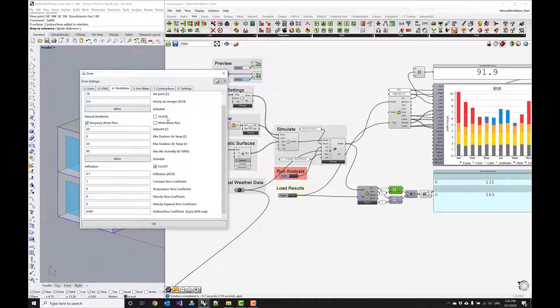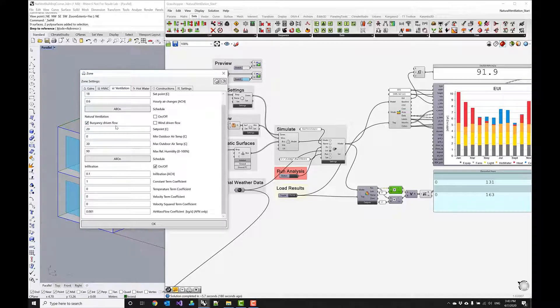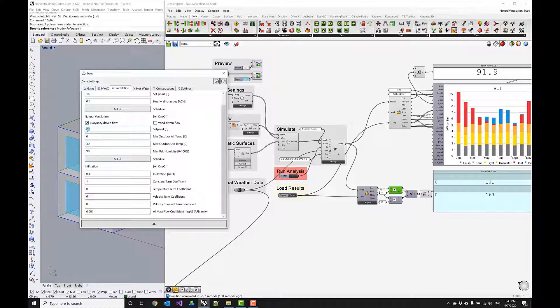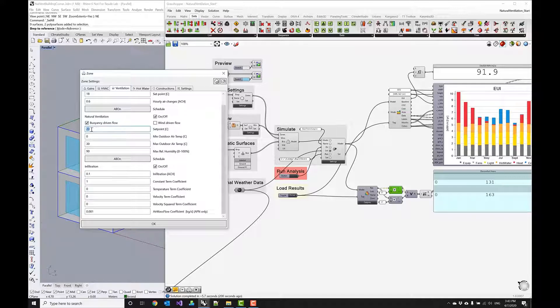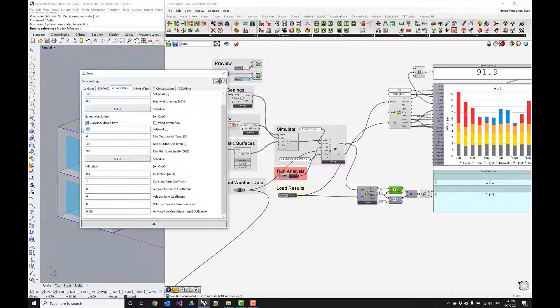So in this tutorial we want to use buoyancy driven flow only and we can think of this as a worst case scenario if there's no wind at all we can certainly count on the buoyancy driven flow. So to do this we can turn this on and then check buoyancy driven flow and then we can provide some set points such as 20 degrees C so we want the system to open the windows until the interior temperature reaches 20 degrees and then the windows should be closed again so this is like trying to cool the building down to 20 degrees C.